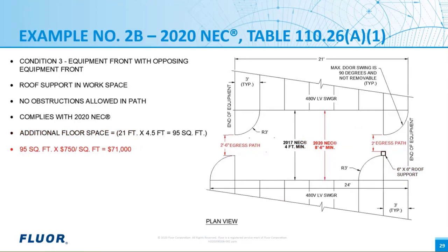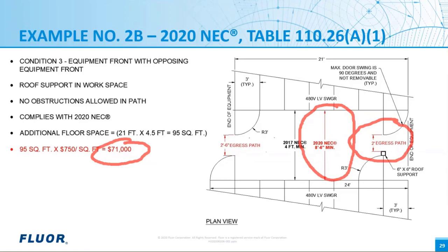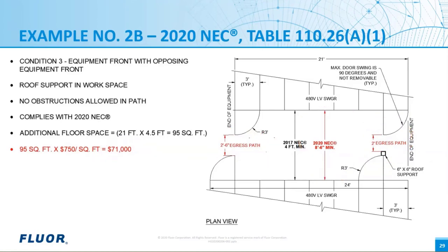Here's another version of what we just spoke about on the previous slide, but this has been modified to allow a roof support obstruction, and this is acceptable per the 2020 NEC. The 2020 NEC doesn't get this detailed, but we understand the intent. The intent is clear. And here the roof support is located on one side of the 24-inch entrance and egress path. So now the minimum dimension front to front between equipment is 8'4", resulting in a cost increase of $71,000 for the floor space between that equipment.